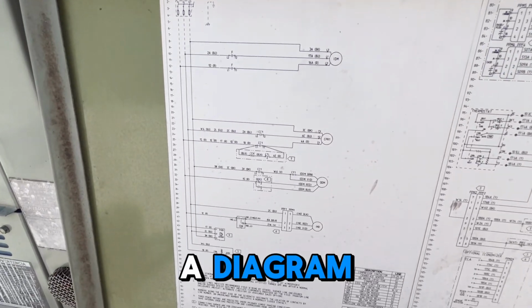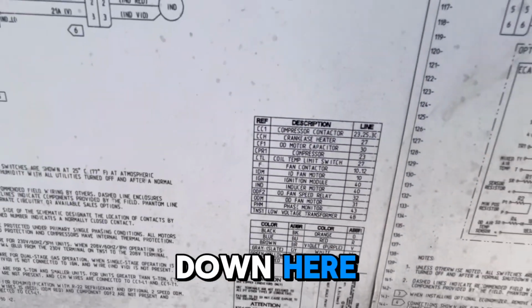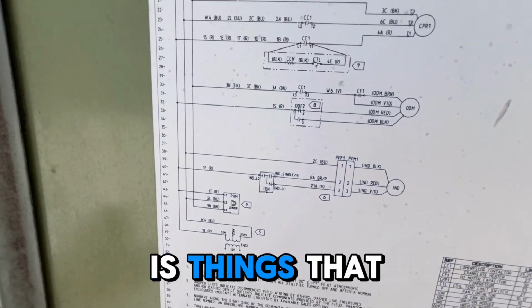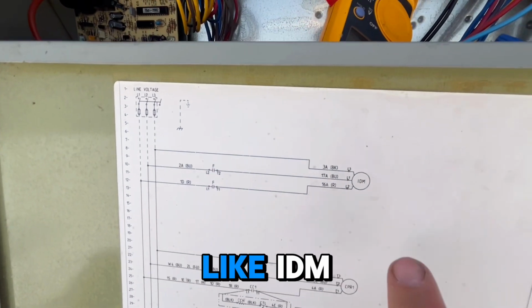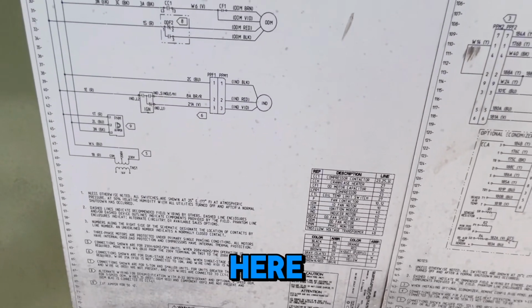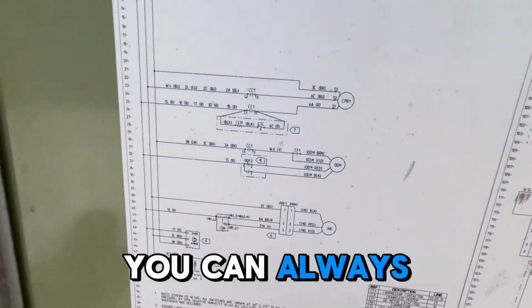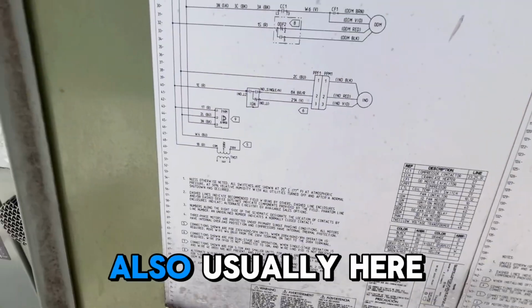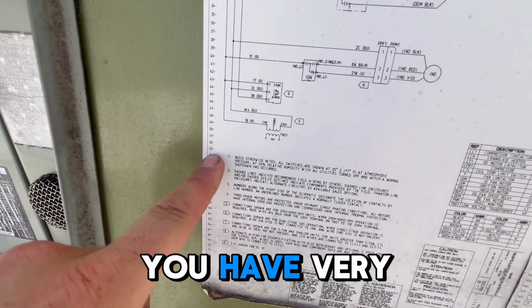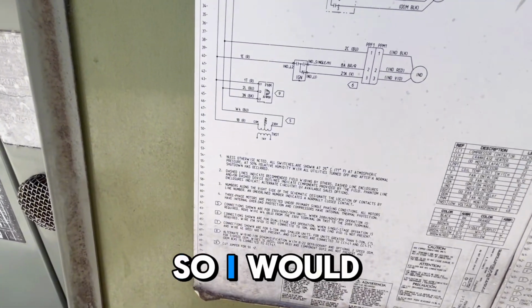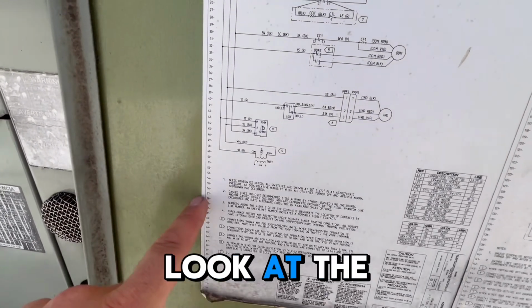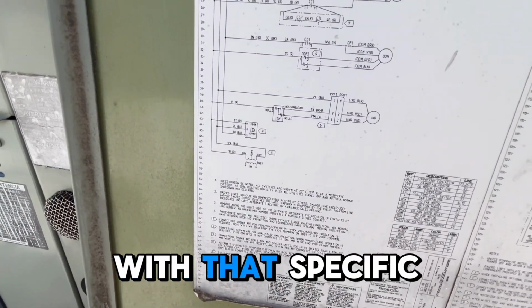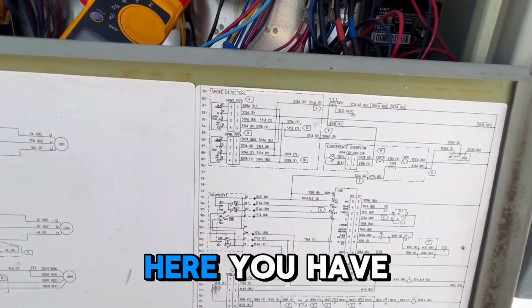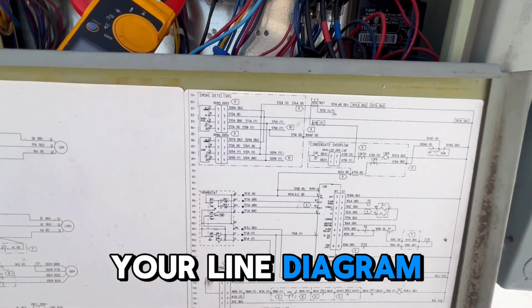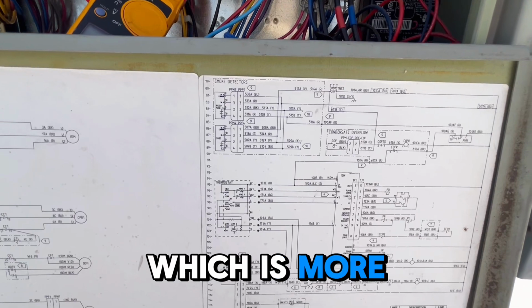That is one thing about electrical wiring diagrams. You always have a diagram and then you have a legend down here. So if there are things that you don't know, like IDM, you go down here: indoor motor. You can always refer to the legend down here. Also, usually here you have very important notes. So I would always look at the diagram, look at the notes, look at the legend to get familiar with that specific schematic.